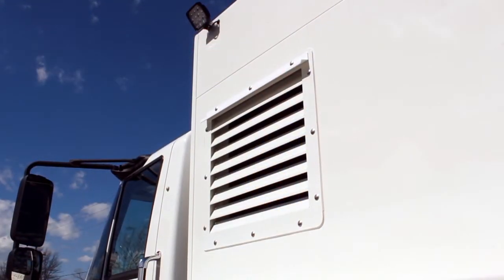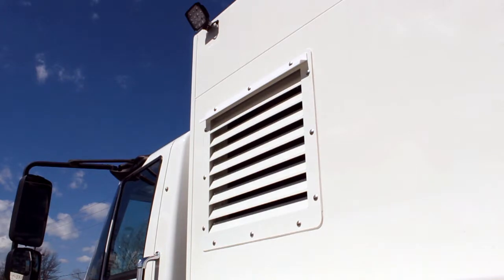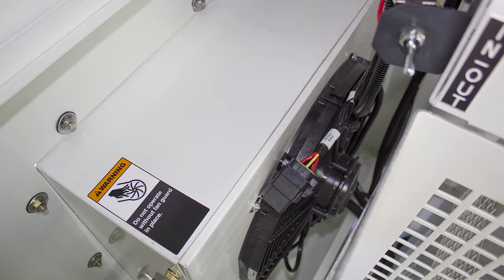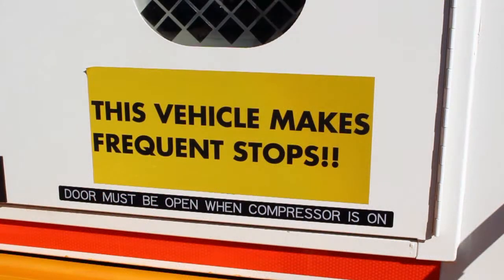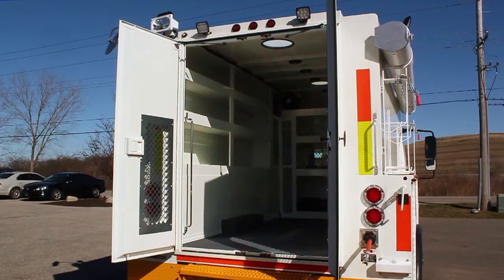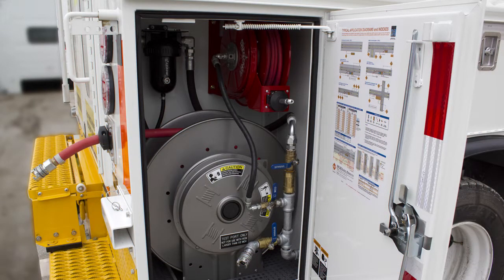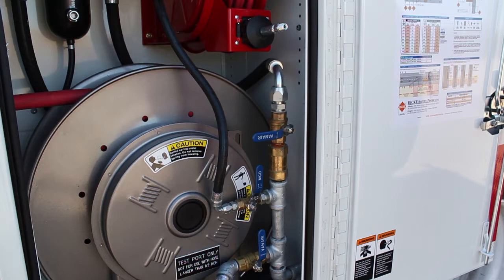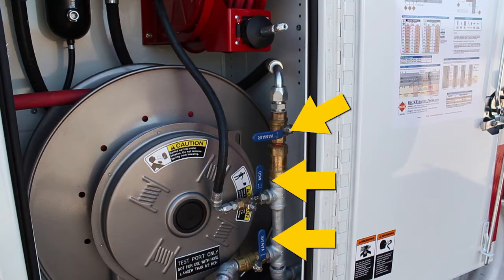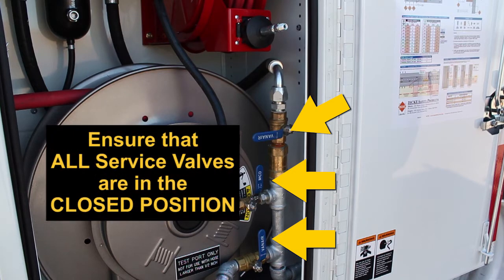Locate the compressor oil cooler. If the cooler is mounted externally, no action is needed. If the cooler is mounted internally, as with this unit, the back doors will need to be opened and secured before operating the system. There are 3 service valves within the hose reel cabinet: the test port valve, the 1/4-inch hose valve, and the 3/4-inch hose valve. Ensure that each service valve is in the closed position.